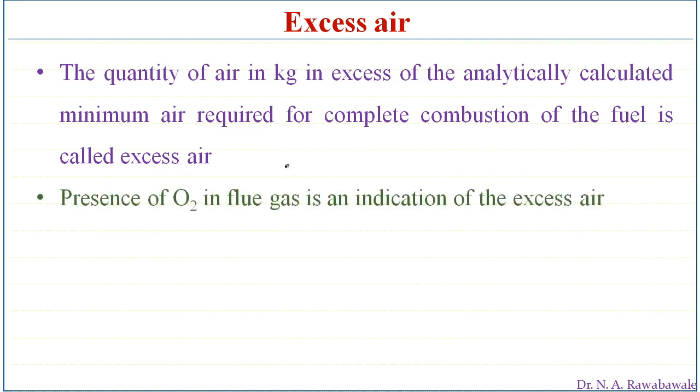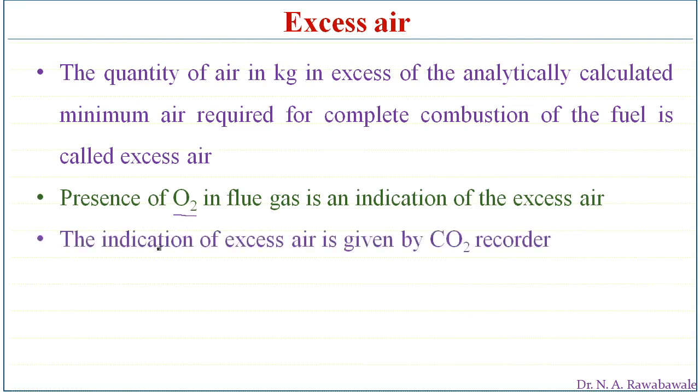Now the presence of oxygen in flue gases indicates that the air supplied is excess. If we supply the minimum quantity of oxygen, then the complete oxygen is utilized for combustion and no oxygen will be left in the flue gases. The presence of oxygen in the flue gas itself is the indication that the air supplied is more than the required air quantity.